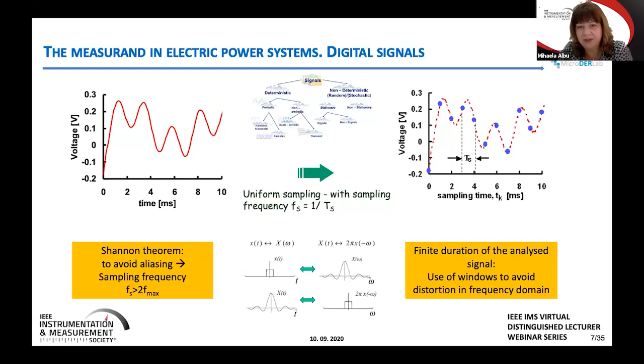Therefore, it's important to check not only data integrity, a kind of buzzword for the PMU area, but also to take a look at the samples and the Shannon theorem, of course, because it's digitalization. This is nothing new, but we must consider that there is always a finite duration of the analyzed signal. So we have to choose the appropriate signal processing windows or time windows to avoid distortion in time domain, meaning Shannon's theorem and the measurement time windows are equally important here.